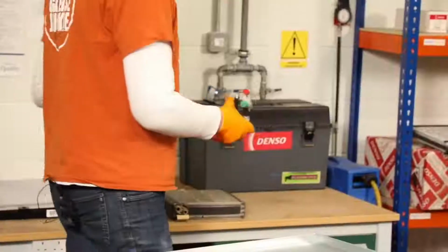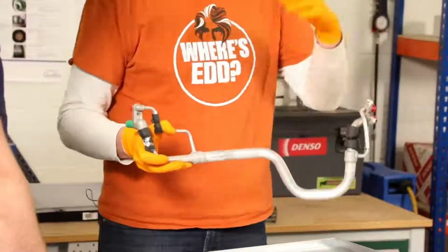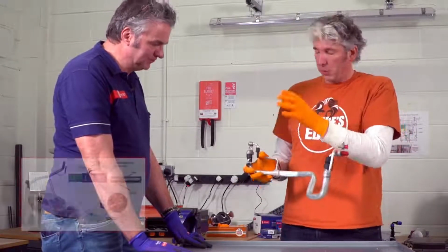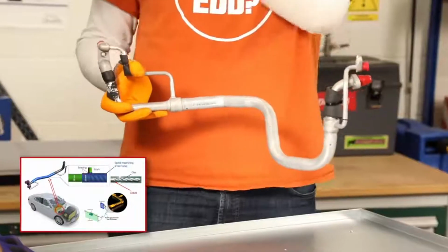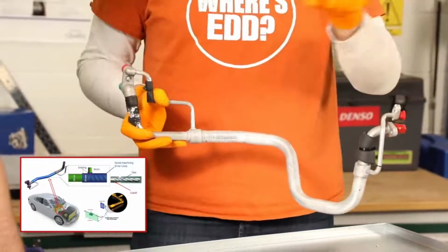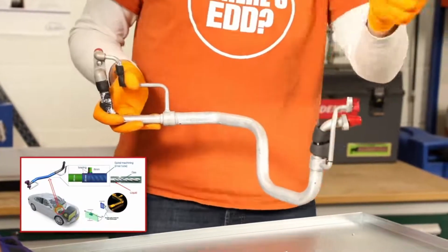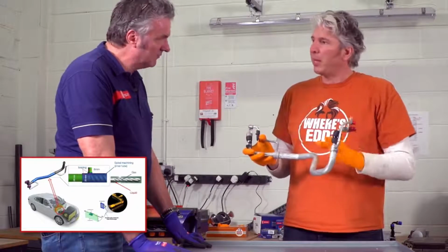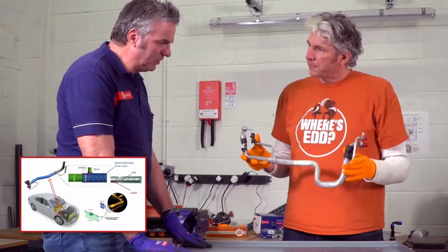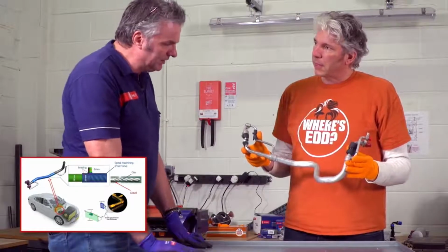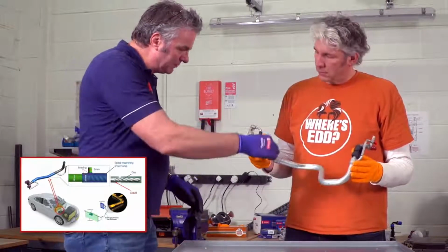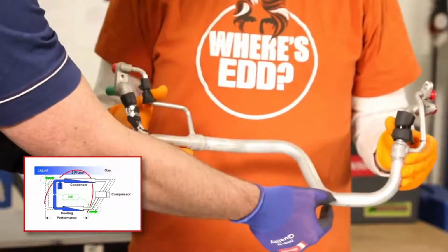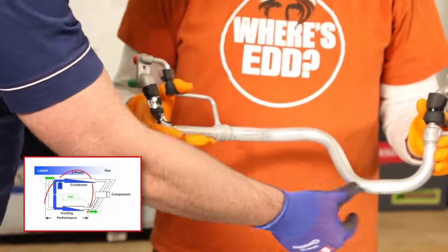Now, we haven't really spoken about plumbing. When you think about it, you've got a condenser, and warm-ish liquid refrigerant is going to get piped from that condenser to the expansion valve, then through the evaporator, and there'll be another pipe coming out from there going to the compressor. But this is quite a clever little innovation. This is actually combining both pipes, isn't it? Yes, correct. We call this an internal heat exchanger. So it exchanges heat. It takes liquid in the outside tube and gaseous refrigerant in the inner tube.